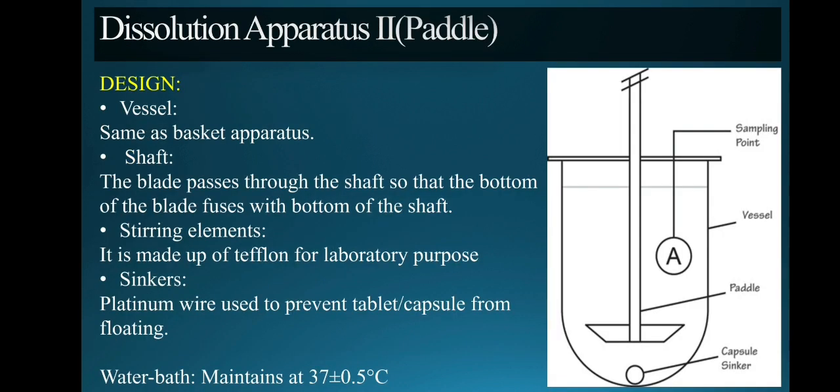Now we move forward to dissolution apparatus 2, that is the paddle. The vessel design is the same as dissolution apparatus 1, which is the basket, but at the end we have a paddle instead of a basket. It is made up of Teflon for laboratory purposes. We also have a sinker to prevent the capsule and tablet from floating. It also maintains a temperature of 37 degrees Celsius.